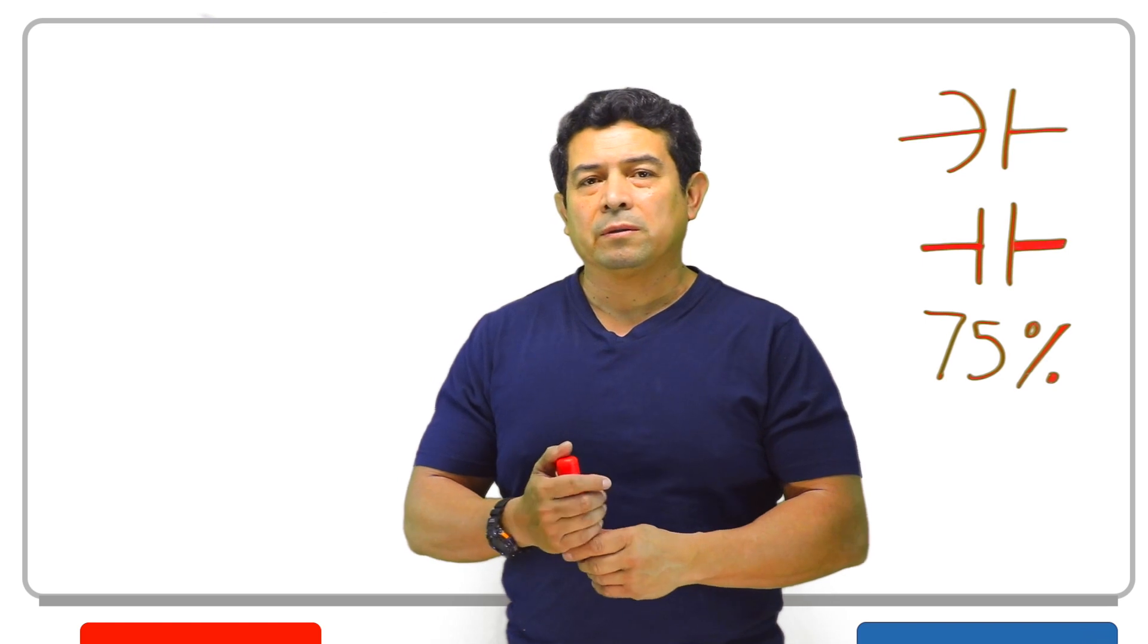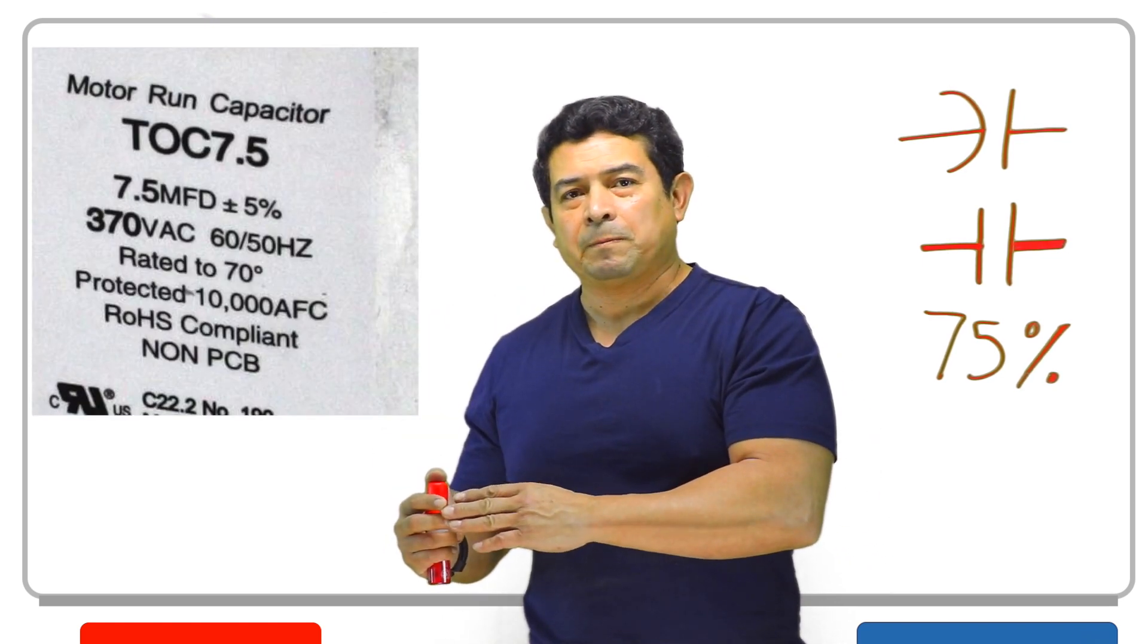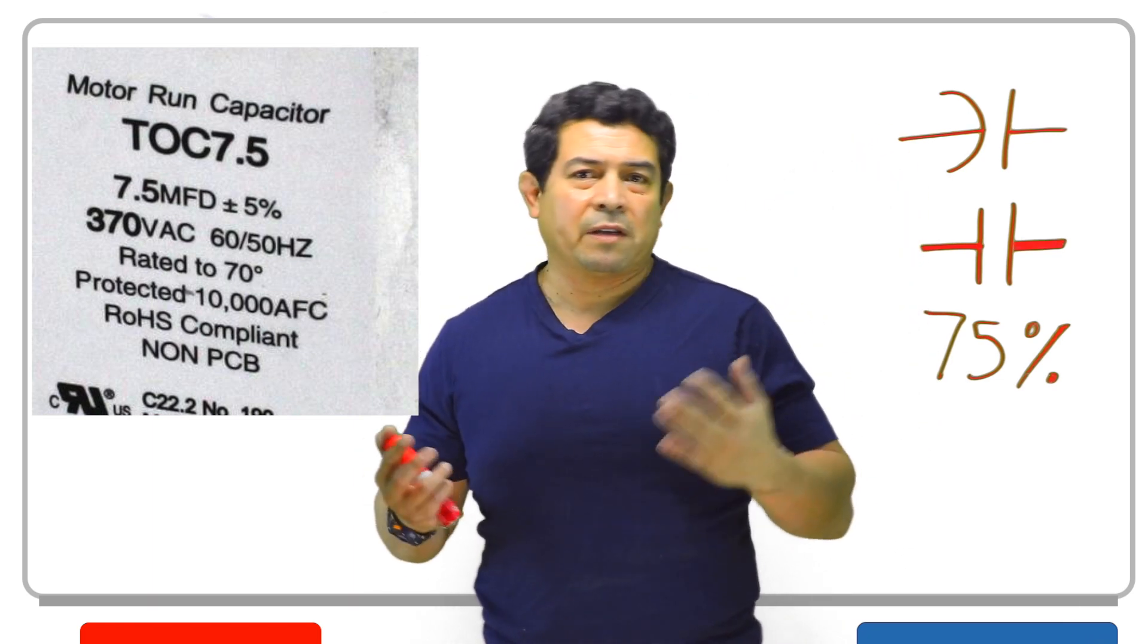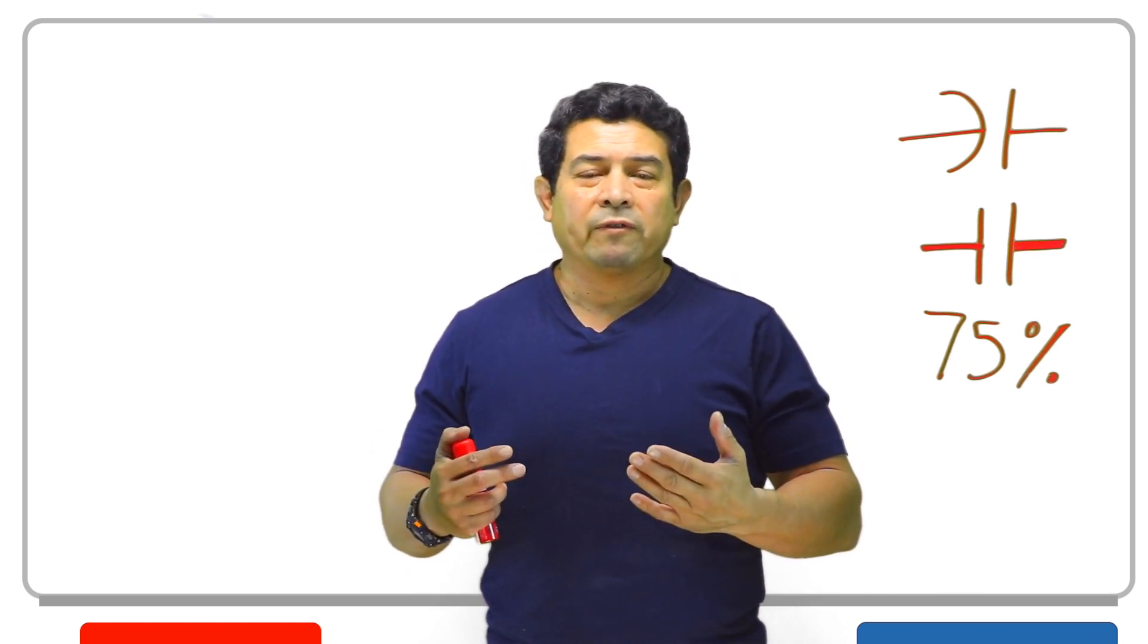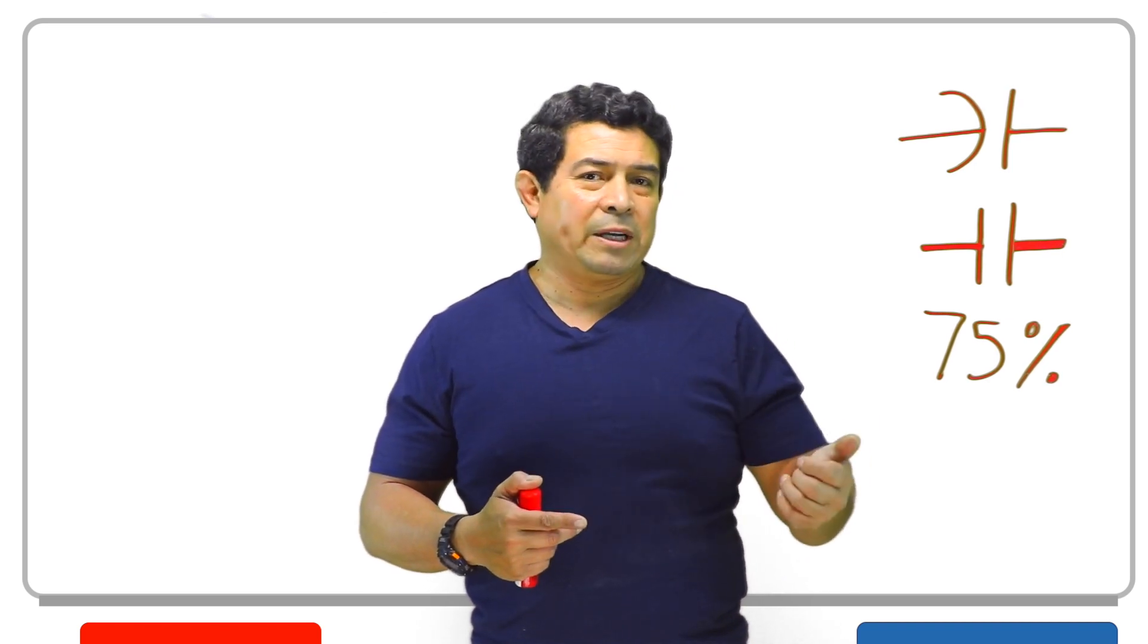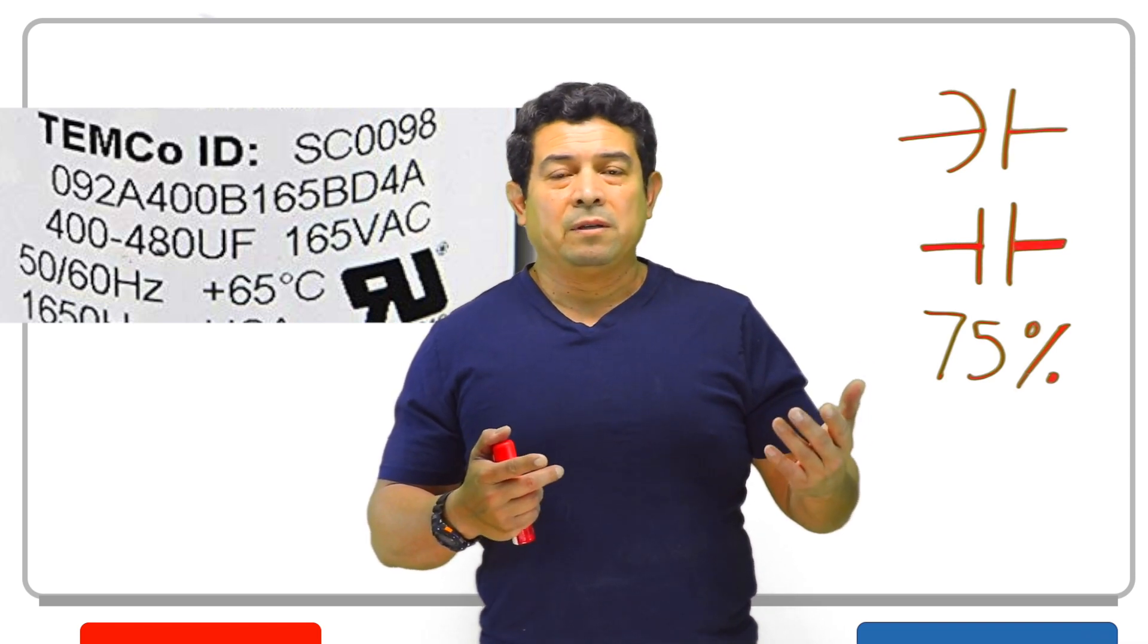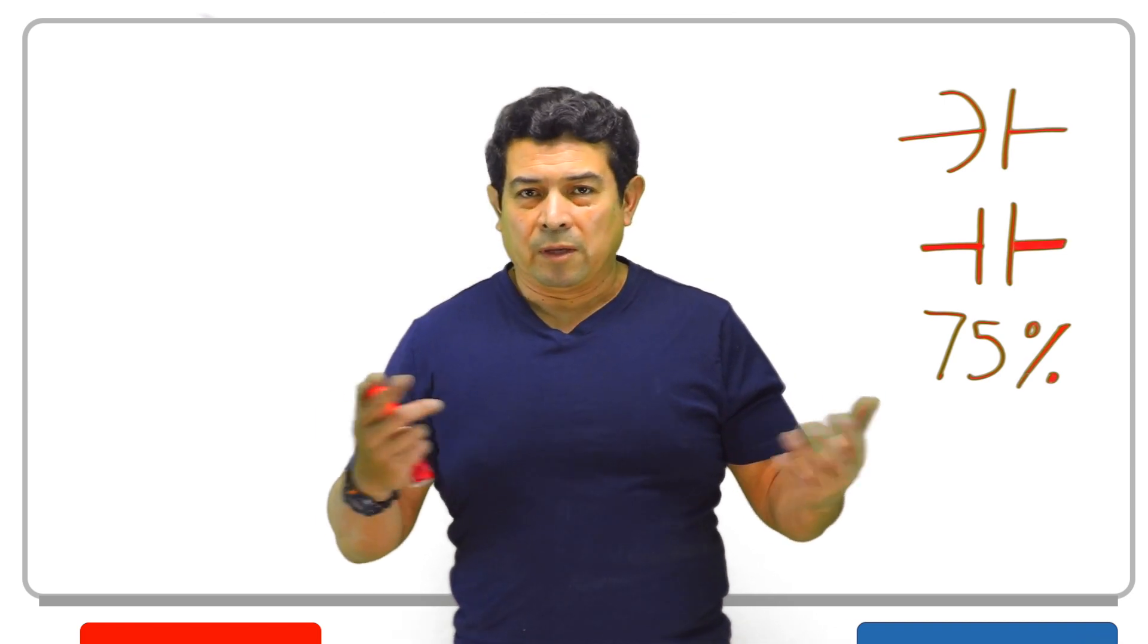The main difference between the two is that the run capacitor is going to be much lower microfarads. When I say low, I mean 5, 7.5, 10, 25, 30, 45, 50 microfarads. A start capacitor, you're looking at 150, 200, 300, 450 microfarads. It just depends. So keep that in mind. That's the main difference.